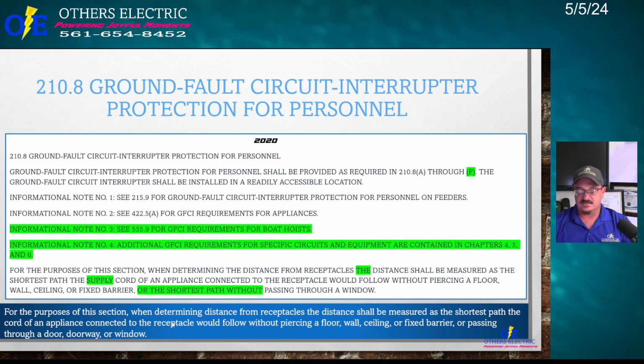Okay, so what that means is, I'm going to tell you, this is how you measure. Let's say the code says anything within 6 foot of a sink has to be GFI protected. Here's what this means. When they say how you measure 6 foot, that's what they're talking about. You're going to take a 6 foot string, and go from the top of the outer edge of the sink basin. You got the sink, and then you got the countertop. So you got to go from the outer edge of the sink, not the countertop, right? If that 6 foot string, or what they call an attachment cord to an appliance, but just think of a string, can reach the receptacle, it has to be GFI protected. Okay?